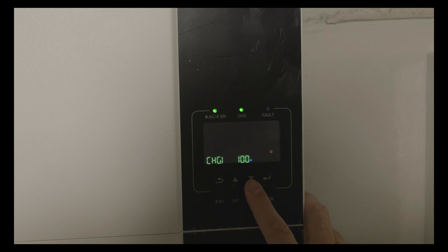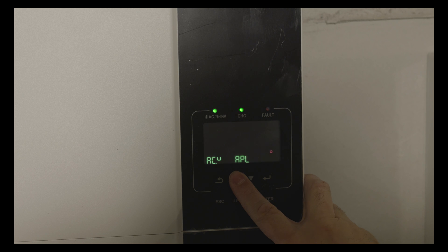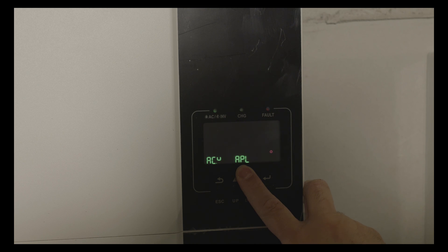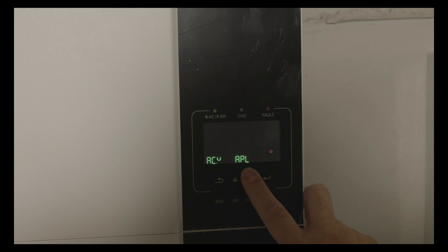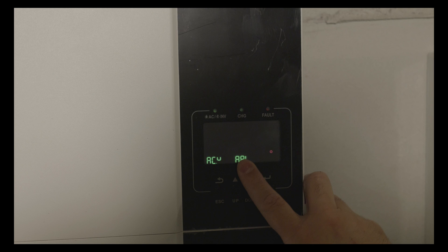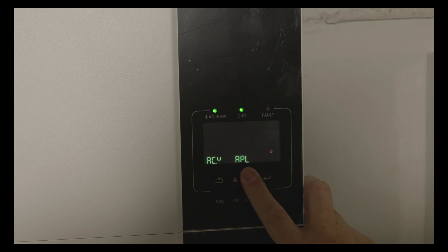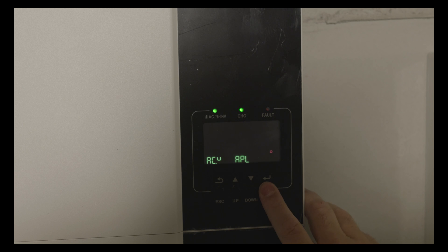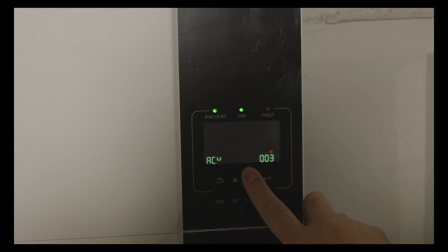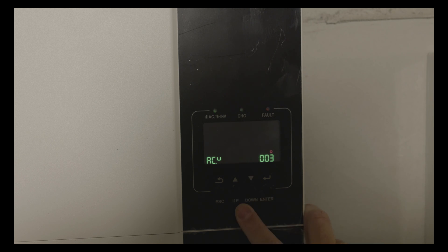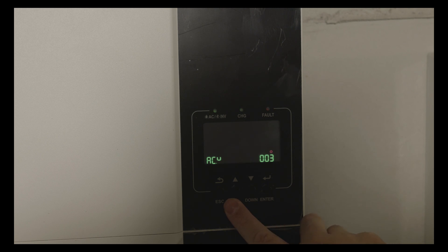Then we have AC input voltage range. I've set it to appliance because I'm using 230 volts that my utility provides. There is an option UPS which is from 170 to 280 volts AC, and generator which is from 90 to 280 volts AC with maximum charging current of 30 amps.